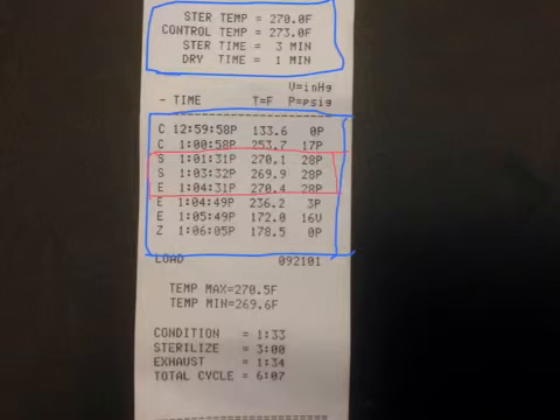You can see that it started at 1 minute after 1 and 31 seconds. So 101, 31 seconds. And then it continued to 104 and 31 seconds. So the first thing we want to do is we want to assure that this is a 3-minute cycle. And so we're going to take the 104.31, subtract 101.31 from that, and we see that there is a difference of exactly 3 minutes.